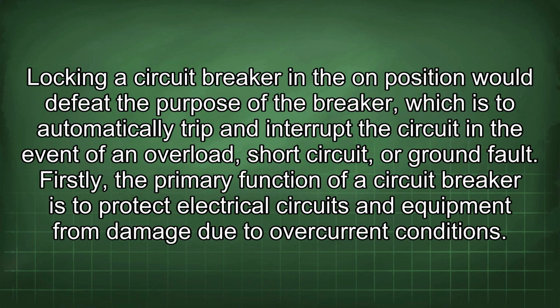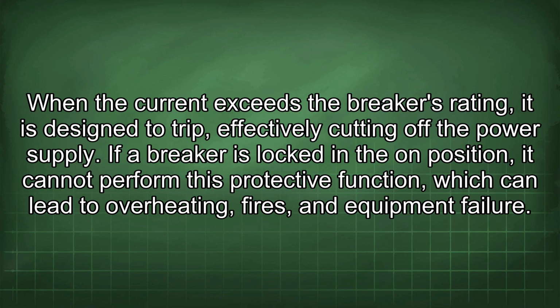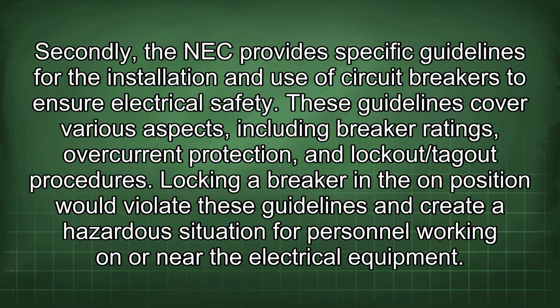Locking a circuit breaker in the on position would defeat the purpose of the breaker, which is to automatically trip and interrupt the circuit in the event of an overload, short circuit, or ground fault. Firstly, the primary function of a circuit breaker is to protect electrical circuits and equipment from damage due to overcurrent conditions. When the current exceeds the breaker's rating, it is designed to trip, effectively cutting off the power supply. If a breaker is locked in the on position, it cannot perform this protective function, which can lead to overheating, fires, and equipment failure.